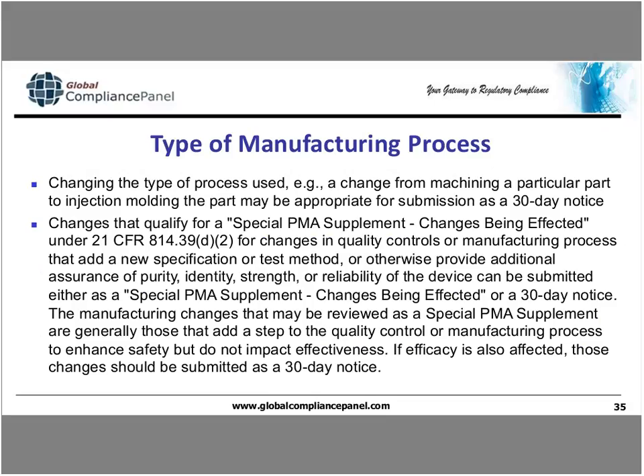Type of manufacturing processes, changing the type of process used. Example, a change from machining a particular part to injection molding the part may be appropriate for submission as a 30-day notice. Changes that qualify for a special PMA supplement, changes being effected under 21 CFR 814.39(d)(2) for changes in quality controls or manufacturing process that add a new specification or test method or otherwise provide additional assurance of purity, identity, strength, or reliability of the device, can be submitted either as a special PMA supplement changes being effected or a 30-day notice.